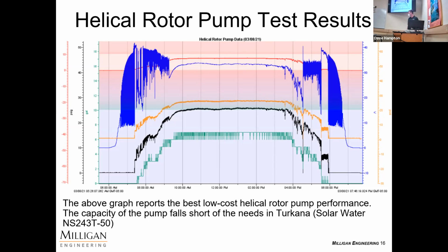And as we've been communicated with the failing pumps, I believe Dr. East was actually able to bring back a film. Yeah, and I think Dr. Harrell said there were scorch marks indicating overheating. So it's very likely that the high current is possible. That's another issue with cooling. The water passing through the annular region around the pump is what cools it, and so if you're just sitting there and building up heat, there's nothing to cool it. So it'll stall? Is low voltage stall then? Yeah, that's your theoretical basis there.